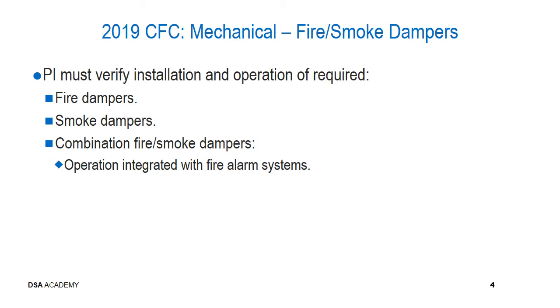The project inspector must verify installation and operation of required fire dampers, smoke dampers, combination fire smoke dampers, and the operation integrated with fire alarm systems. 2016 NFPA 105, Section 7.5 Acceptance Testing notes that acceptance testing of smoke dampers shall be performed by a qualified person with knowledge and understanding of the operating components of the type of assembly to be tested. Section 7.5.2 goes on by stating that before testing, a visual inspection shall be performed to identify any damage or missing parts that could create a hazard during testing or affect the operation or resetting of the component.